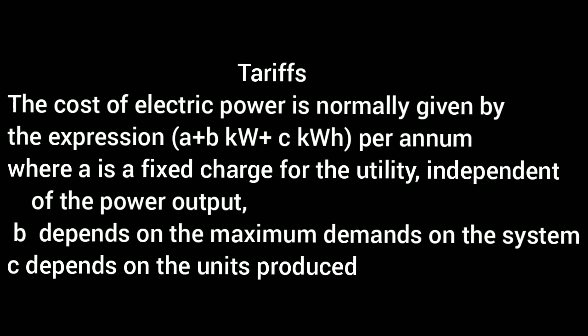Next we can discuss the tariff. The cost of electric power is normally given by the expression A plus B kilowatts plus C into kilowatt hours per annum, where A is a fixed charge for the utility, independent of the power output, B depends on the maximum demand on the system, and C depends on the units produced and therefore on the fuel charges and the wages of the station staff.